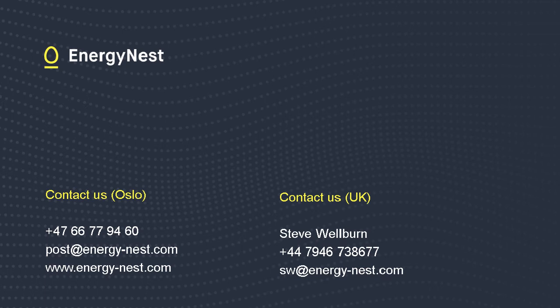The next question is from Gintas Kacinskas. What are the rough efficiencies of converting various energies to thermal energy and then converting it back? Overall, the efficiency of the heat exchanger and the thermal battery is quite high, 97-98% in terms of heat to heat. For electricity in and thermal out, this is also relatively efficient. It's a matter of heating an oil using a liquid heater, so that's also very high efficiency. Heat in, heat out, and power in, heat out are very close to unity, except for the thermal losses of the system.